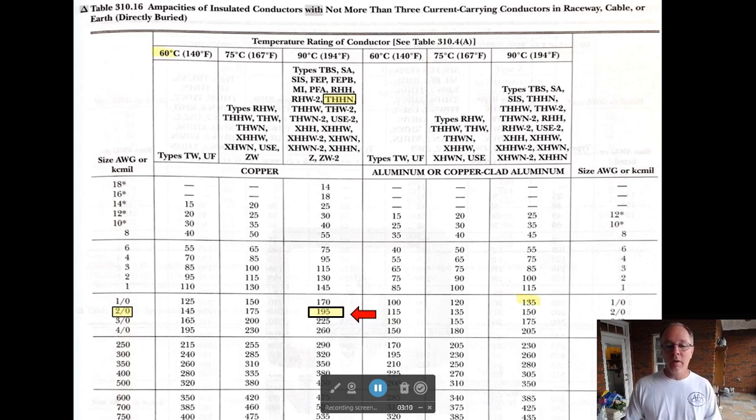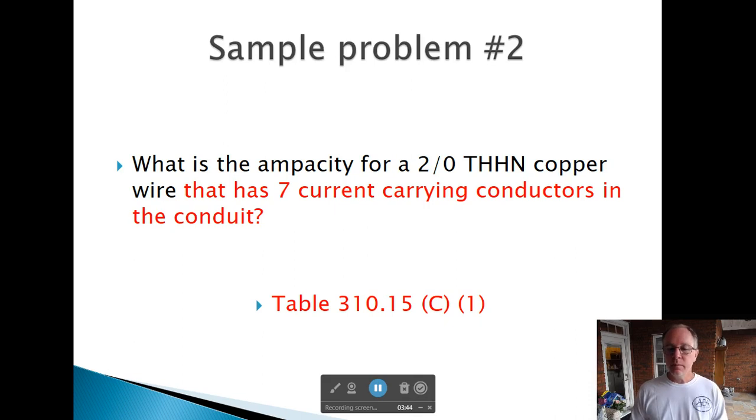If you're looking for 4-Aught THHN, you do the same thing, or number 6-TW. You see 6, you see TW, and follow the chart. This is the first thing you do on every question. You'll find what size wire, what size insulation, and the type of material—copper or aluminum. As soon as you find those three, you go to this table and you establish a number on your ampacity. Then we're going to go up or down from that number.